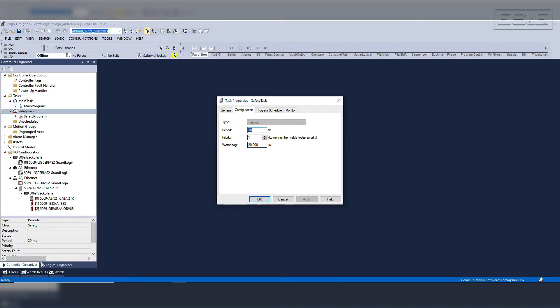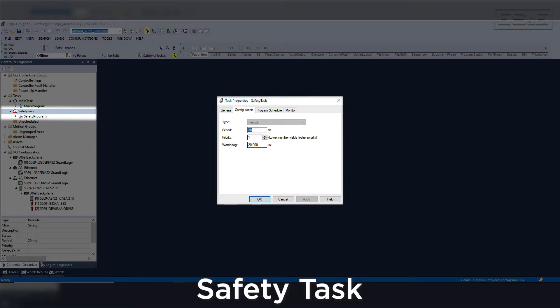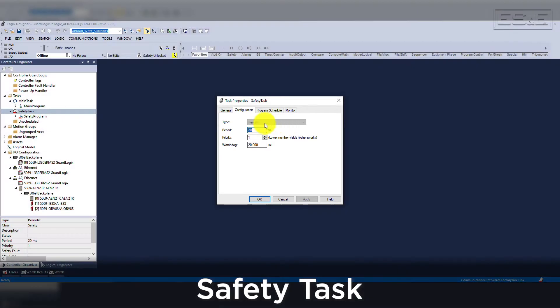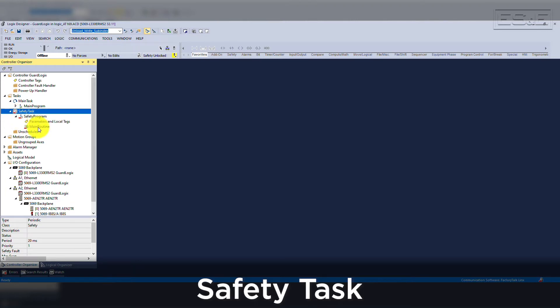When working with a GuardLogix controller, the project will automatically create a periodic safety task that cannot be removed. This task will house all of the necessary routines and configuration pertaining to safety only. Within the task, you will be able to utilize safety class tags, and it is the only location where you can drive a safety output.